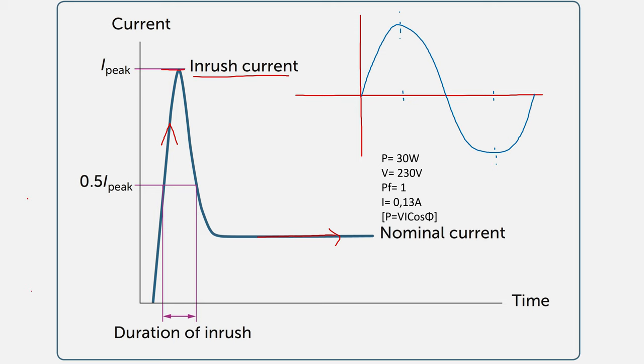The nominal current is the current that the floodlight uses under normal conditions. For example, if we install a 30-watt LED floodlight and assume the power factor is 1, the running current would be 130 milliamps or 0.13 amps. So under normal conditions, a 30-watt floodlight operating at 230 volts would only use 0.13 amps — that would be the nominal current.